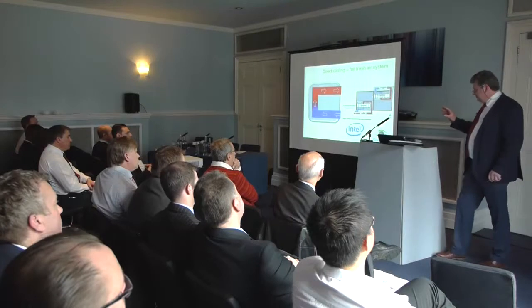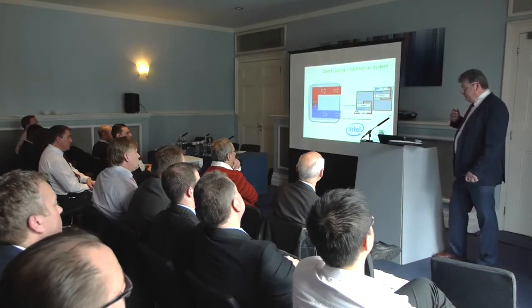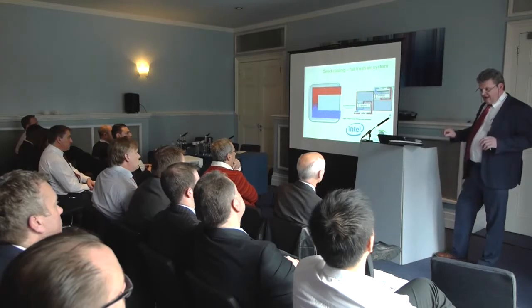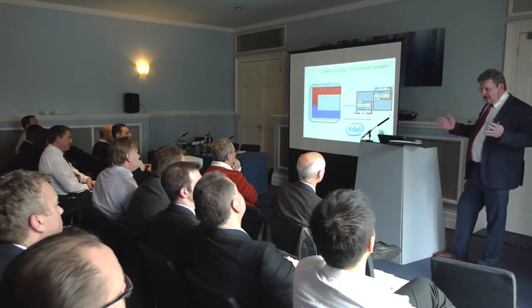Intel did a study out in the desert where they just put in what they call an economizer, which is just a fancy name for a fan, and ran two high-density data centres alongside each other for a while and claimed massive reductions in cooling energy and no significant failures of equipment, and this stuff was just covered in dust. The kit was covered in dust. However, that's a totally unacceptable solution for almost anyone I know.